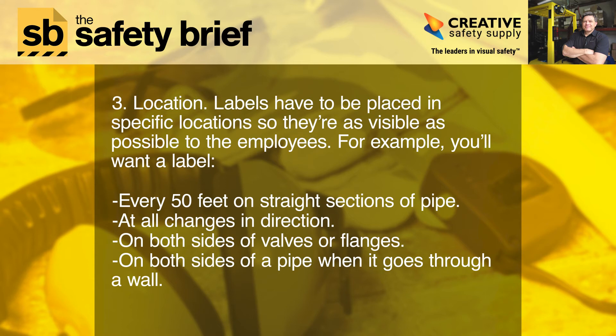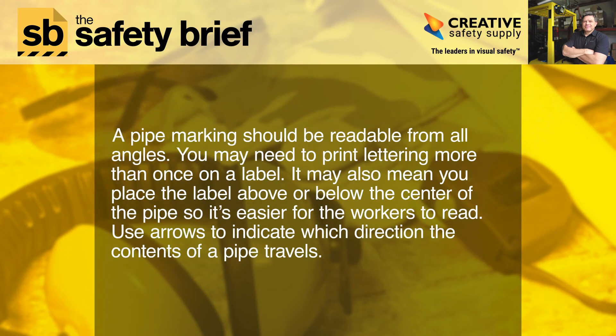Three: location. Labels have to be placed in specific locations so they're as visible as possible to employees. For example, you'll want a label every 50 feet on straight sections of pipe, at all changes in direction, on both sides of valves or flanges, and on both sides of a pipe when it goes through a wall.